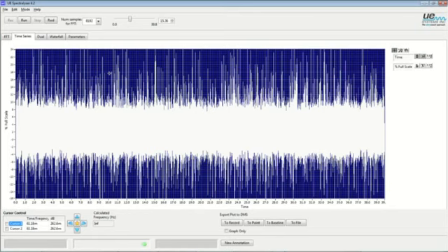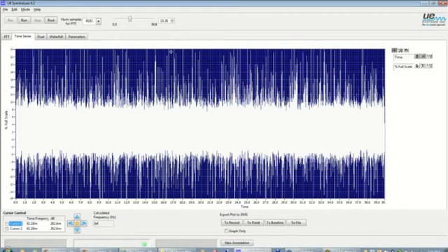These events do not draw current, so it would not be detectable with an infrared camera. But it does damage the insulation, and it starts a path to ground, which subsequently can lead to an electrical arc over or flash over event. So that's the first thing I'm looking for in the time analyzer, is these spikes or deviations from the center line that vary or change in amplitude.